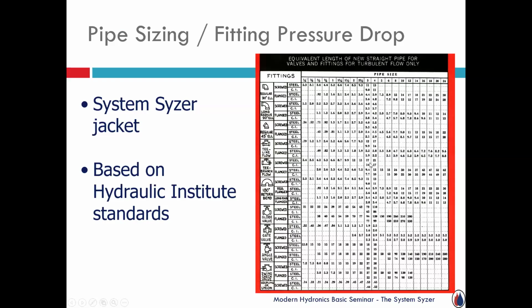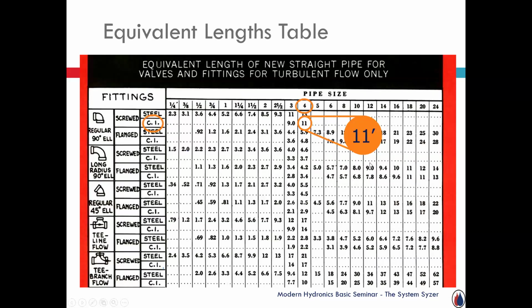So anyways, on the jacket, for those that are online, remote, when you receive the System Syzer in the mail with your shirt and certificate, there'll be a sleeve. And on the backside of that sleeve, and again, it was useful years ago, they were just showing an example of different fittings that would have been used back in the day, and whether they were steel or cast iron, screwed or flanged. But just a quick example, we're saying, hey, what's the equivalent length of straight run if I had a 4-inch cast iron 90-degree elbow? That's all it's saying right there. It's equal to 11 feet of pipe. So if I had a bunch of them, I have to account for that.